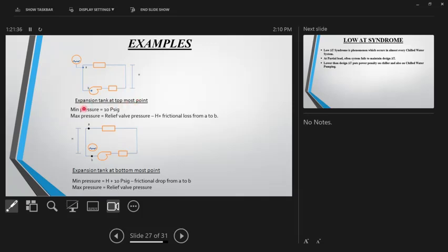See, it is important to understand that 10 psig is not the pressure in the expansion tank. It's the minimum pressure at the minimum pressure point. So if your tank happens to be at that point, then it's 10 psig. But if your tank is somewhere down the line, it is 10 psig plus the static head, and that's the minimum pressure in the tank. So that's how the values of P1 and P2 are decided and used.